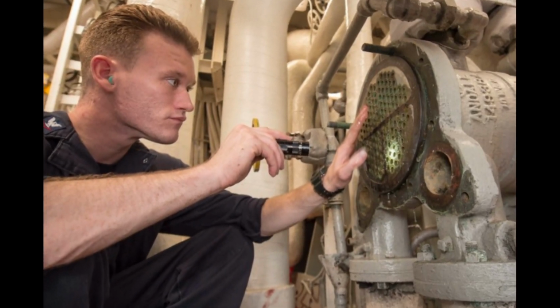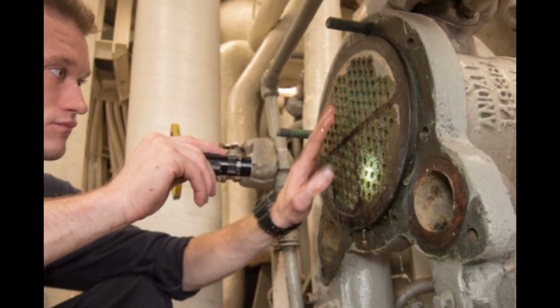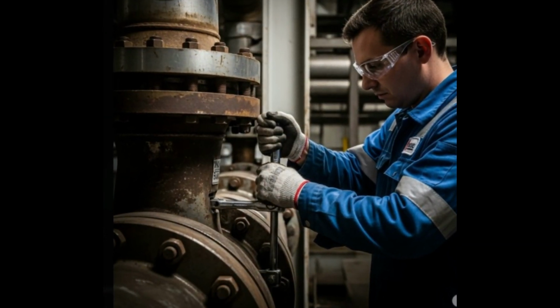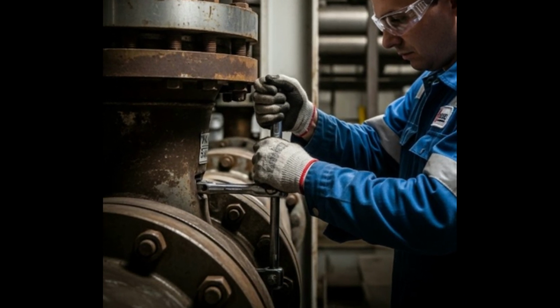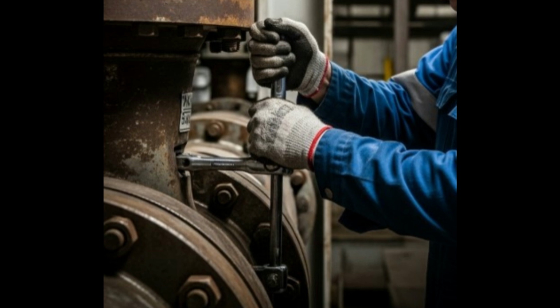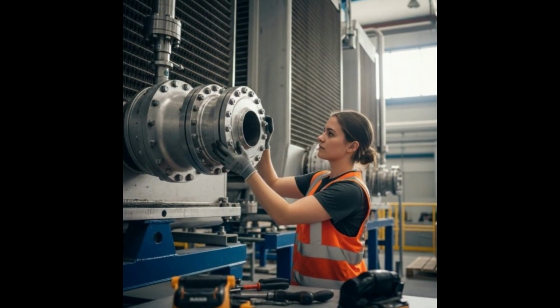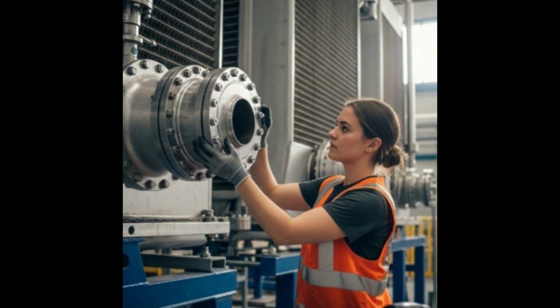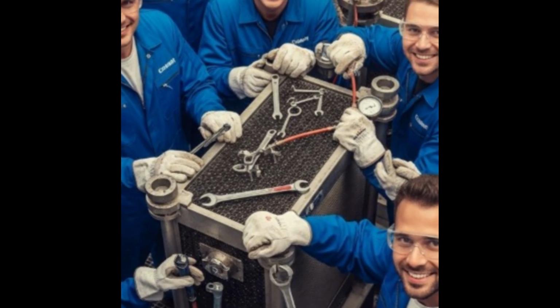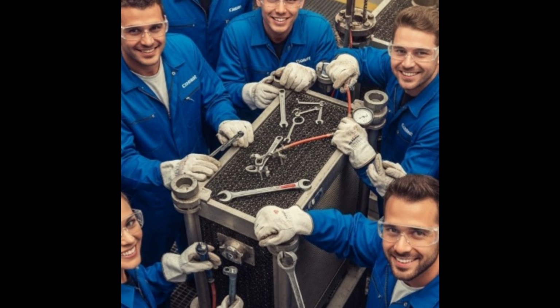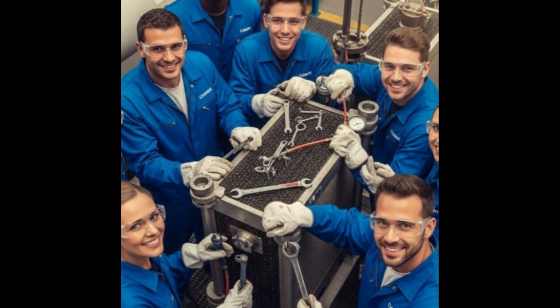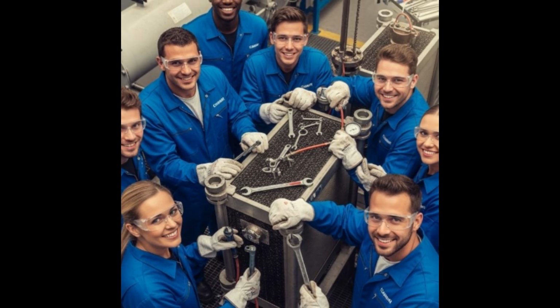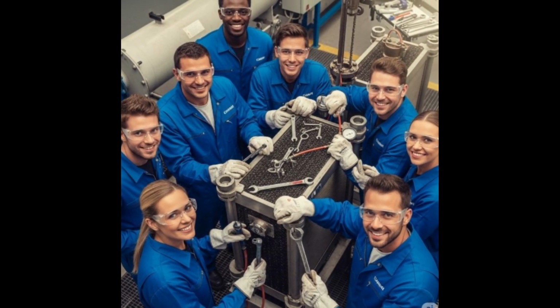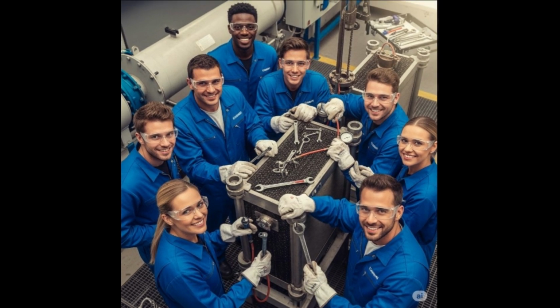Solution procedures include gasket and seal replacement. Worn or damaged gaskets are a common cause of external leaks. Retorquing. Bolts on flanges may need to be retorqued to the manufacturer's specifications to ensure a proper seal. Component replacement. Cracked tubes or plates often cannot be repaired and must be replaced. Proper maintenance of LNG heat exchangers is a proactive investment that safeguards personnel, optimizes plant efficiency, and extends asset life, and ultimately contributes to the economic viability and environmental responsibility of LNG operations.